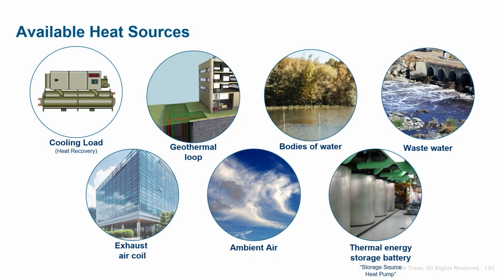But in terms of keeping a more constant source temperature, the mass of the Earth and its bodies of water can be stable sources. Designers are becoming more creative and using other waste heat sources from the building, which is just another form of heat recovery, using wastewater or air leaving the building. And finally, thermal energy storage can provide a relatively compact energy storage from which to draw from where space is limited. Now that the central plant loads, temperatures, and heat sources are known, a central plant system type can be selected and design can begin.